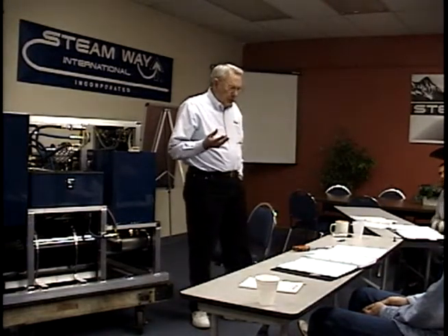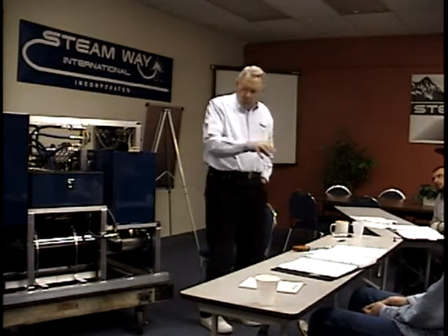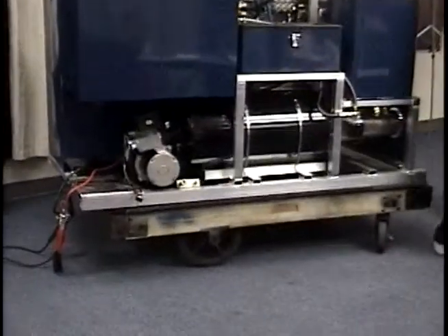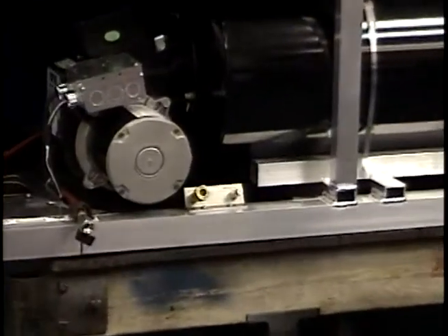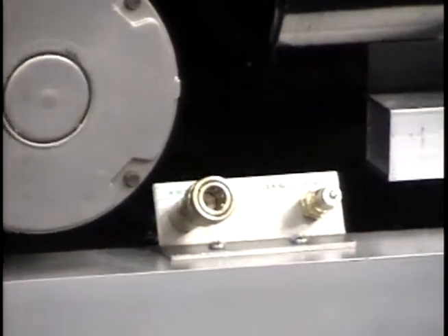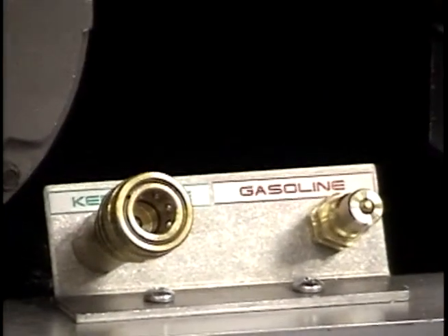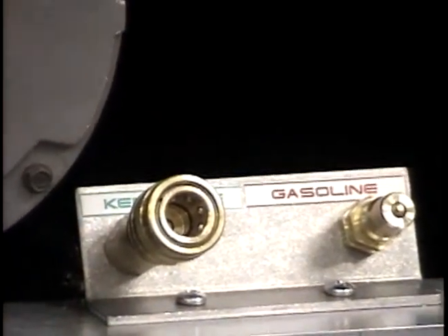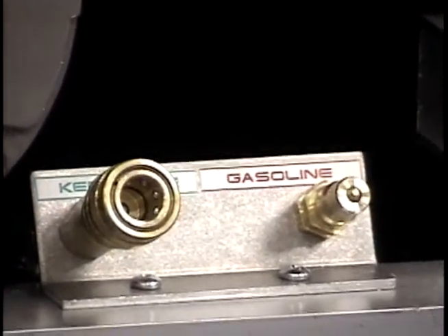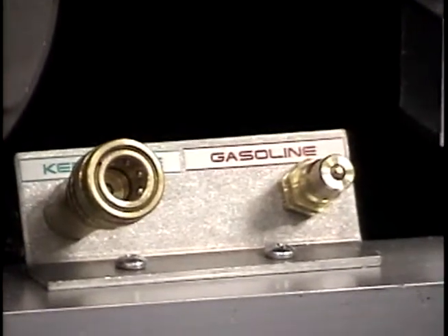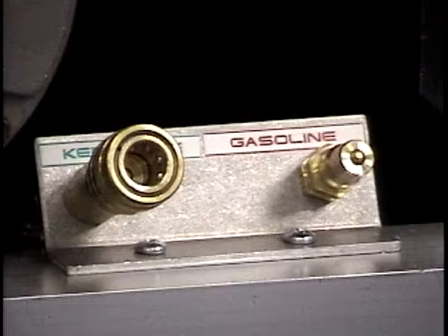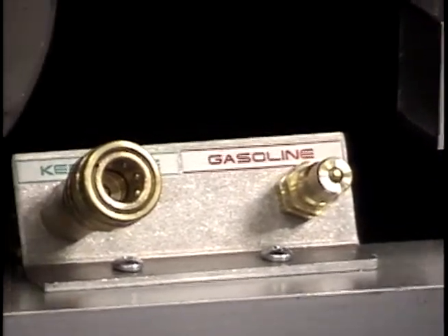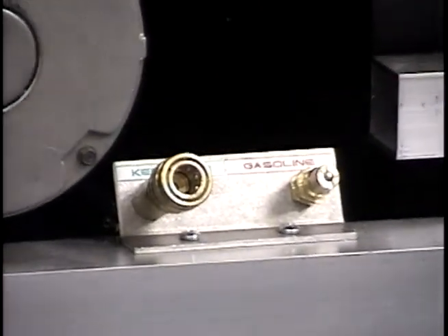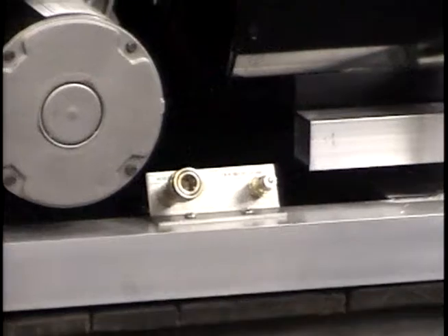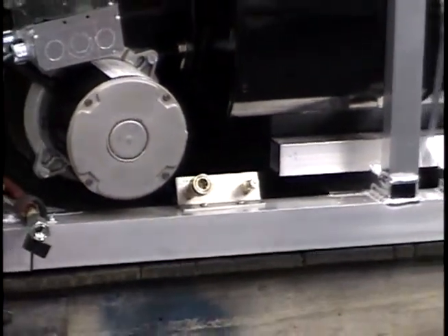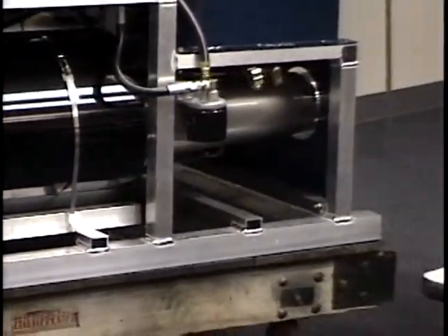As I was about to say, you have a kerosene tank. You have a hose from the kerosene tank to the machine, to the kerosene input, and it's like a boat tank. It has a little squeeze ball on it, and the first time you fire this up, or if you run out of kerosene, what you need to do is hook your hose onto your kerosene tank, and before you hook it onto your machine, it has a male QD, and you push down on the hose on the concrete or something and squeeze the squeeze ball until you get all the air out of the system. Most generally it'll work, it'll come right on and start working right away. If you'll pump it a couple times after the burner starts, you'll get that nice little bubble of air out of the system.